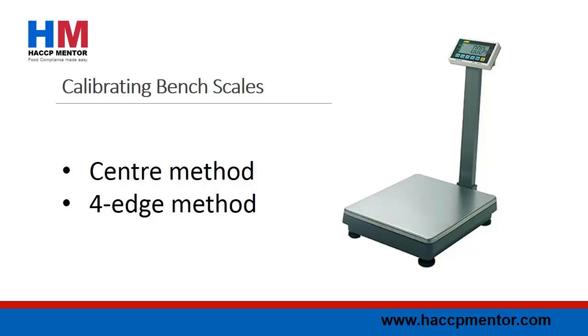To complete the 4-edge method, place your calibrated weights in each of the four corners of the scale plate. For the bench scale to be reading correctly, the display weight should be equal to the sum of the calibrated weights used.